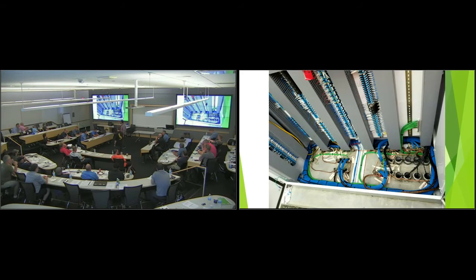This is a project I worked on. As you can see, all of those blue wires have a specific purpose. I had to go through three levels of prints to verify that all of my terminations were going to the correct terminal block, because the worst thing that can happen is you terminate to the wrong terminal block. It makes troubleshooting incredibly difficult.